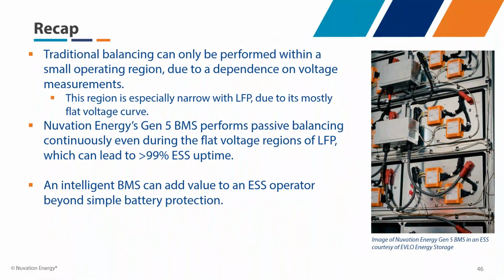Traditional balancing can only be performed within a small operating region, especially with LFP cells, where you only get good correlation between state of charge and cell voltage at the outer ends - high or low state of charge. One advantage of continuous balancing is that you can balance the system more of the time without having to hold it at a high state of charge. This gives you higher ESS uptime, in excess of 99%, because you don't have that need to hold at a high state of charge.